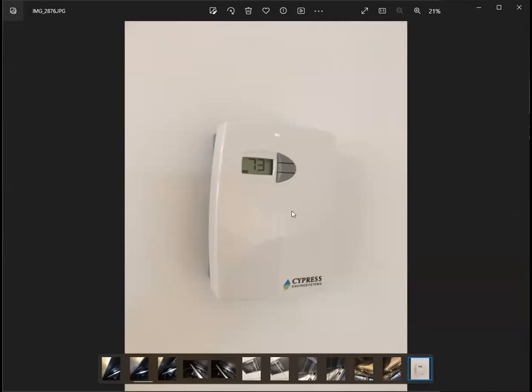This is a thermostat. So you need to identify the location where it was installed. This inspection will fall on the HVAC control systems. So it's under energy inspection. So you need to make sure that it was functional, installed for each VAVs or AC units. So it should have an individual control as per drawing specs or as per manufacturer specifications.